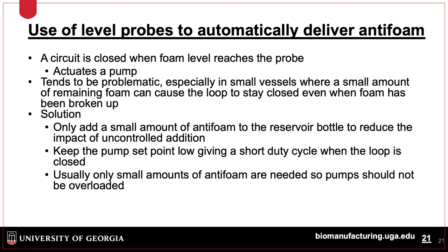In combination with antifoam are foam level probes. There is a feedback loop where foam is detected by the level probe, which actuates a pump that adds antifoam. The pump stops when foam decreases, but can be problematic if the level probe is too sensitive. This problem is ameliorated by having a small amount of antifoam or short duty cycles when the pump is activated. This issue is more pronounced in fed-batch culture, which will be covered in the next lecture.